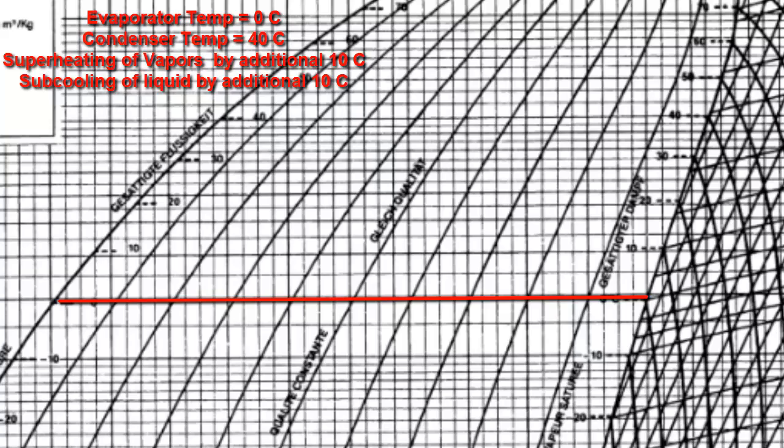First, we will draw a line for the evaporator temperature, which is 0°C, shown on the saturated liquid curve. We draw a horizontal line until it meets the saturated vapor curve. However, we will need to extend this line further into the superheated region because the vapors leaving the evaporator are superheated by an additional 10°C.